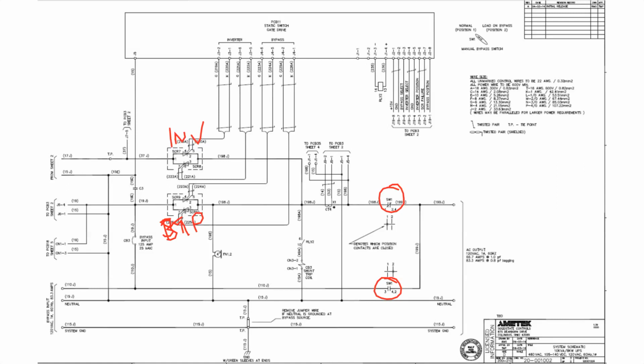We are getting away from that design. That used to be our old design where we had a bypass switch on the front of the UPS. But basically, we are encouraging everybody to get away from that design and move to a remote manual bypass switch, which I'll discuss in just a moment. But when I say a manual bypass switch, not a remote manual bypass switch, then I mean it's inside the UPS. Okay? So you can see here in normal operation, this switch 1 is closed.